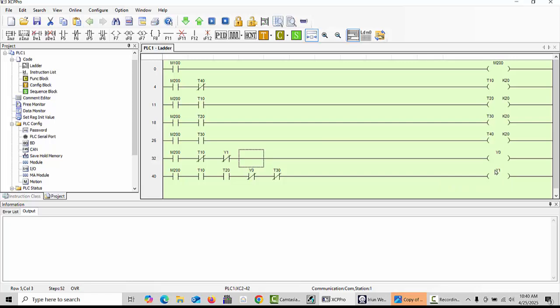this open contact we use for Y1, and inside this is T20 and T30, which we use for delay, means when starting reverse to forward, when the motor goes, however much delay we would like to put, a delay must be put. We use 20 seconds for all. You can change this one, no problem. And also when going forward to reverse, we also need the delay. So we are using this T20 and T30 for the delay for the reverse to forward.